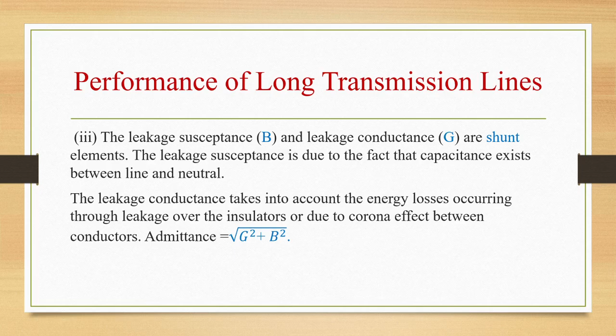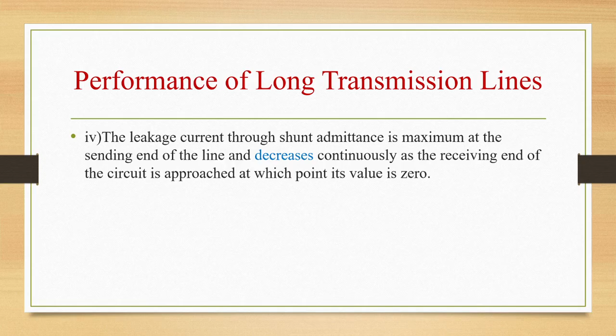Leakage conductance takes into account the energy losses occurring through leakage over the insulators or due to corona effect between the conductors. Admittance is given as root of G square plus B square. Fourth point, leakage current through shunt admittance is maximum at the sending end of the line and decreases continuously as the receiving end of the circuit is approached, at which point its value is 0.